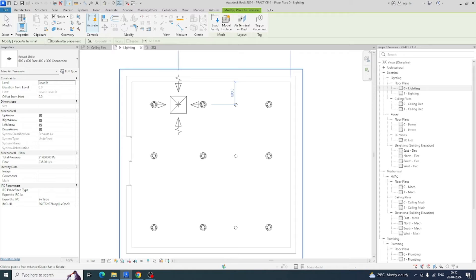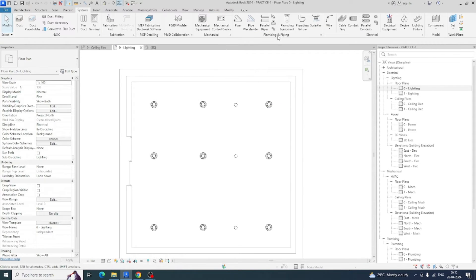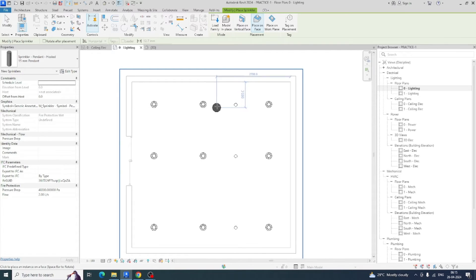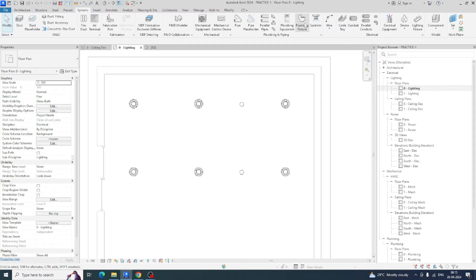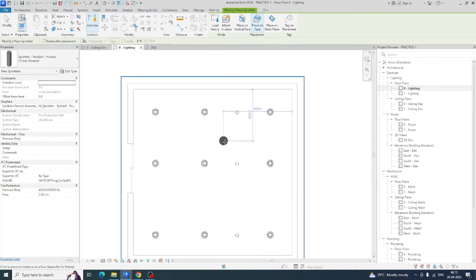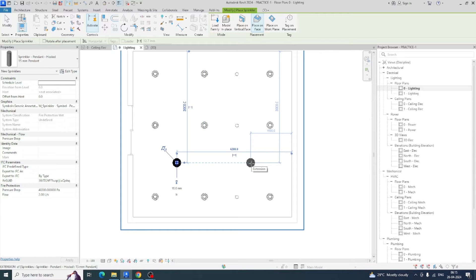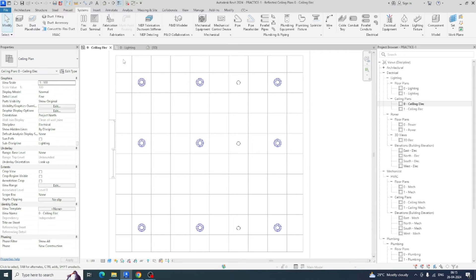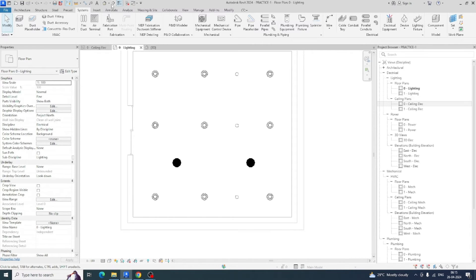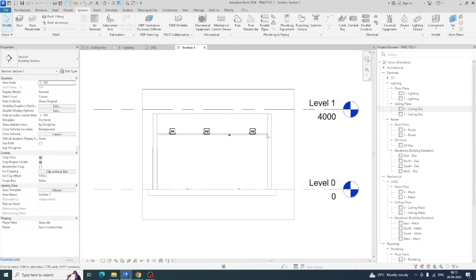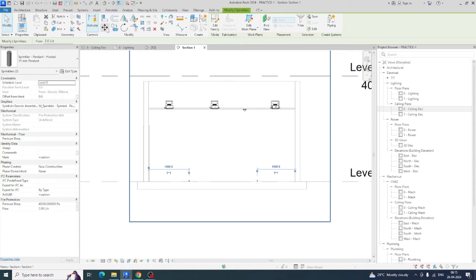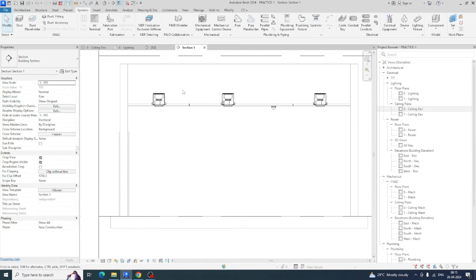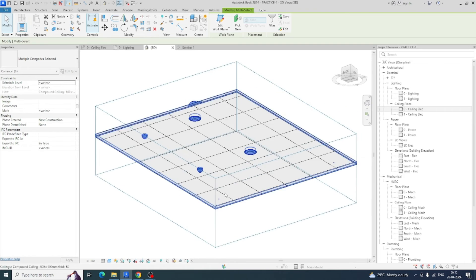As per the size of the ceiling you can place those items. Sprinklers also you can place — just go here and place from there. I'm fixing one sprinkler here and another sprinkler here. Go to the view to check if they are at the proper height. If not, go to Edit Work Plane, pick a plane, and pick the ceiling so the sprinkler will snap onto the ceiling.